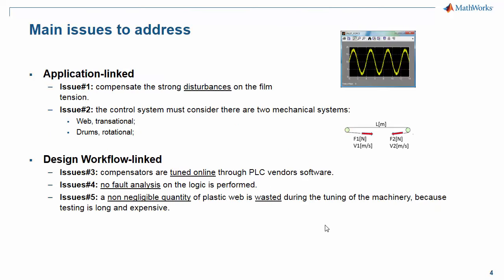However, this application is not trivial at all. Here are some of the issues associated with it. First of all, we have application-linked issues. For instance, compensating adequately the strong disturbances on the film tension coming from the part of the system preceding the region under control. And the fact that the control system must consider that there are two mechanical subsystems interacting together: a translational mechanic associated with the web system and a rotational mechanic associated with the rollers rotating around their axis.